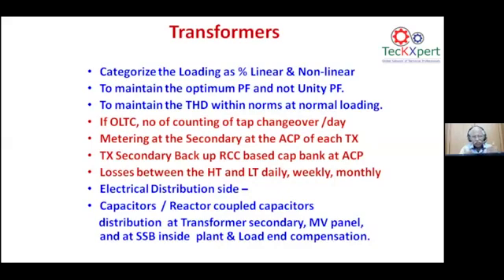Next to this is the electrical distribution side, where the reactors or capacitors, what distribution is there and how much is there. If there are more non-linear loads, let us say we have a lot of VFDs in the system, this is supposed to give you a power factor of always around 0.95. That is what the branded VFD OEMs claim. From no load to full load, for a given equipment and a given loading, the VFD is going to maintain a power factor of 0.95. That means that much amount of capacitors can definitely be switched on in the existing electrical distribution side, and then try to maintain the power factor between 0.95 and 0.96.